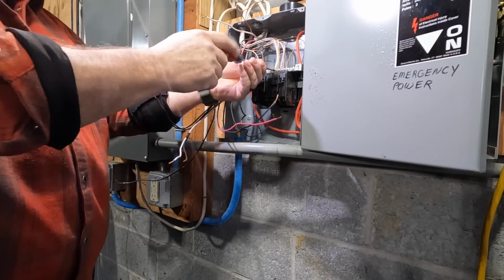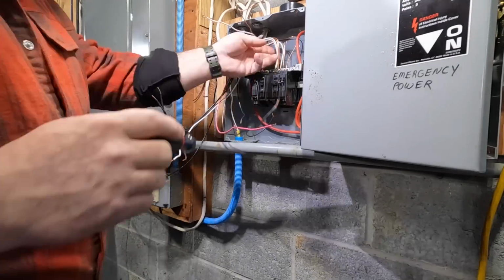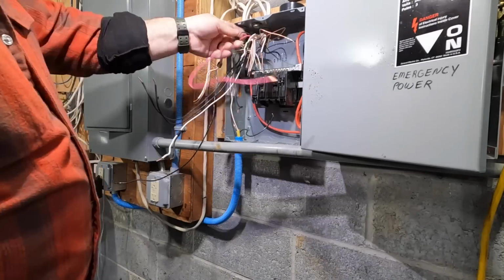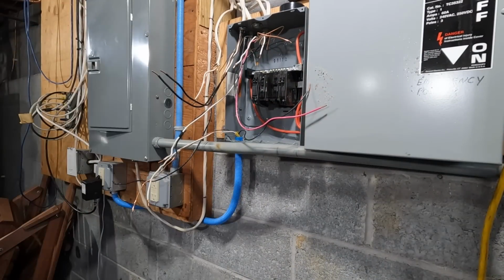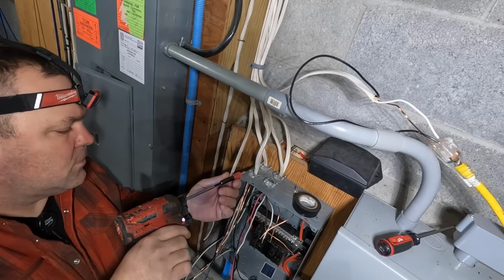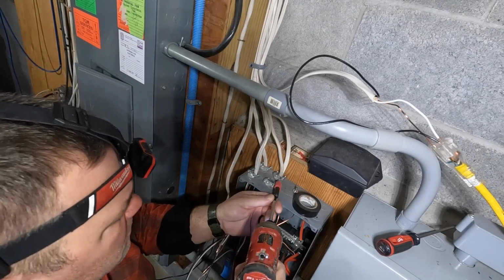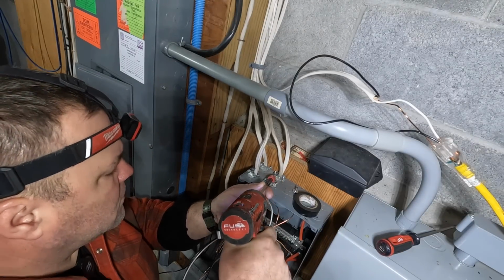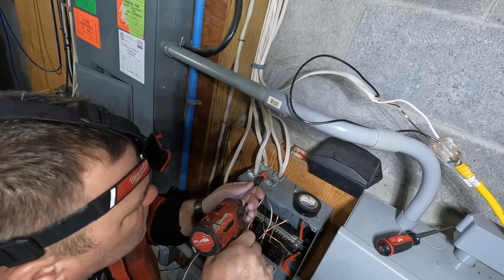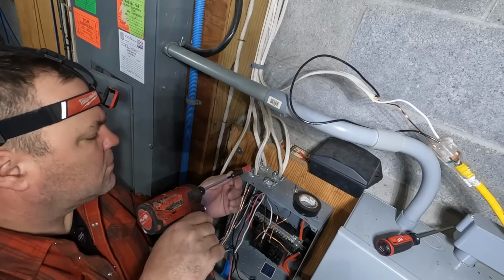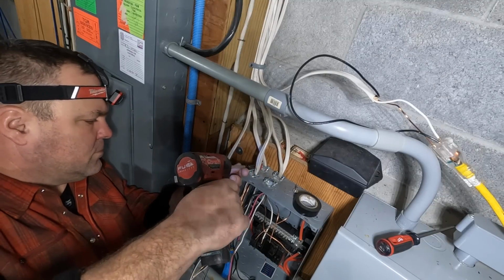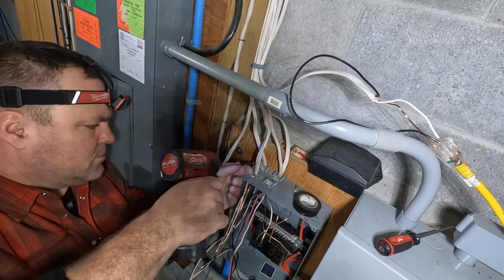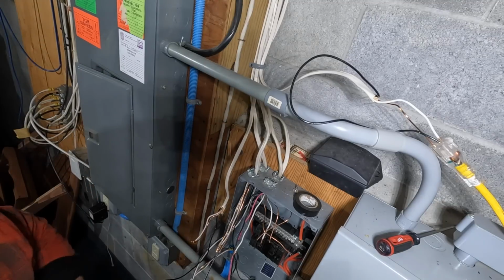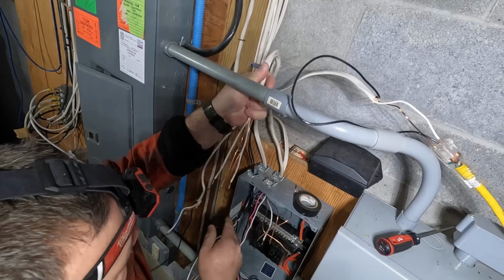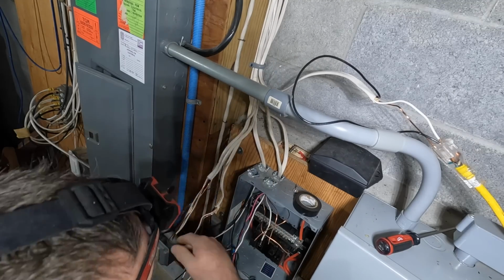Actually, what I meant to say is that if you have 19 amps on one leg and 15 amps on another leg, that neutral current is going to add up to be 34 amps on the neutral. And for a number 12, it's much too small, and you will have issues. To alleviate this issue, we put one of the ungrounded legs to L1 and the other ungrounded leg to L2, and now the neutral will carry the difference between both of the legs. So if you have 19 on one and 15 on the other, the neutral will carry 4 amps. By the way, could you hear the boiler stop after it was satisfied by the thermostat? That's what that noise was.